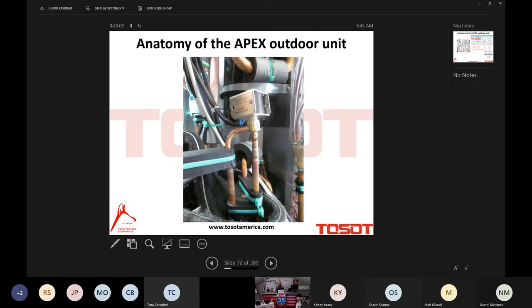The TXV in the heating mode is doing nothing, absolutely nothing. Just the opposite in the cooling mode. In the cooling mode, the TXV of the indoor unit's doing the heavy lifting, and the EEVs of the outdoor unit, nothing at all. And how that happens, my friends, the easiest way I can describe it is through this electromatic valve. It's a bypass, ladies and gentlemen, for lack of a better description.